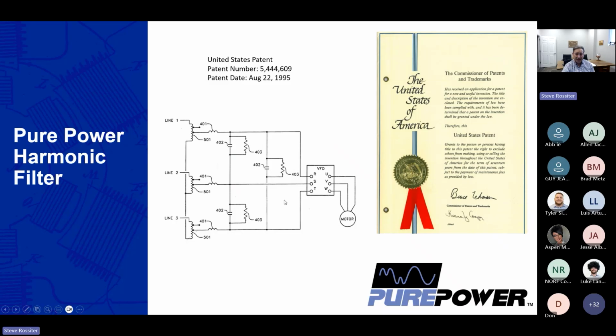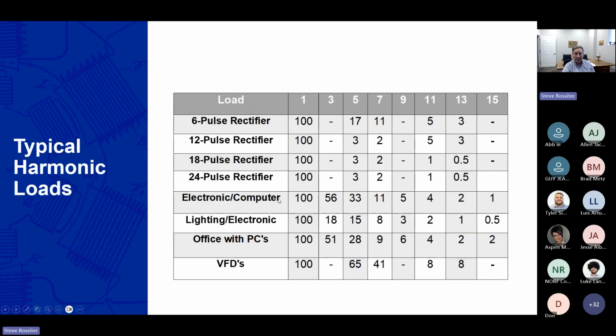But still, we find today this is one of the most economical ways, using passive harmonic filters to mitigate the different types of harmonic distortion. This just shows quickly, a VFD could have 65% fifth harmonic and 41% seventh, but even your computers are going to be way up in there unless they have new harmonic corrected power supplies, like some of these newer LED lights that are a little bit more expensive, but that's solving the problem on the equipment side of things, office PCs and so forth.